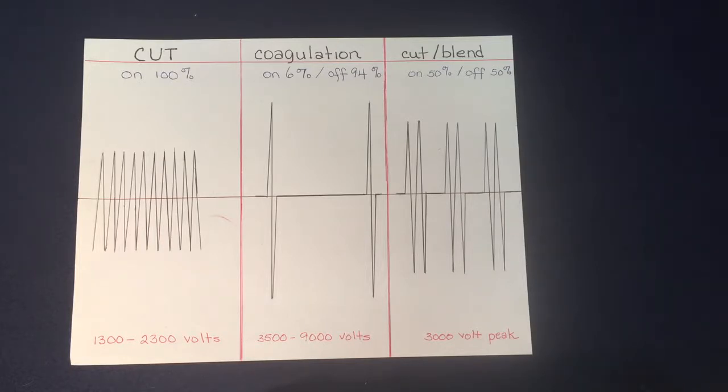On the left-hand side here we see the cut. When the cut is on, it's going to be on 100% of the time and that's why you see those spikes. The voltage is going to be 1300 to 2300 volts, and because it's constant, that heat is constantly being applied. It's going to vaporize the cell and the heat is dissipated in the vaporization of the cell.